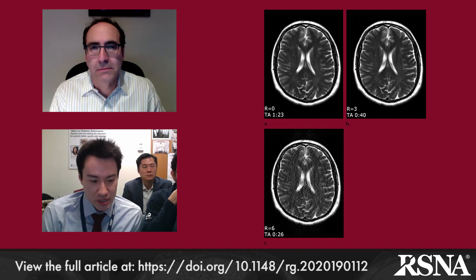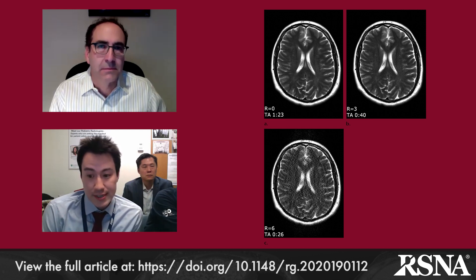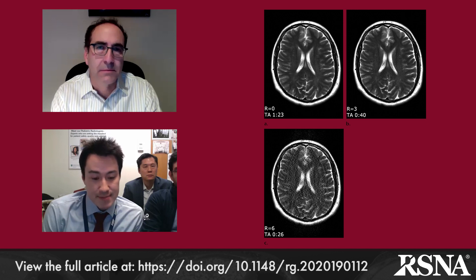There are a number of different strategies to accomplish parallel imaging, some based on eliminating aliasing in the imaging domain, some in the K-space-based domain. All of them are essentially equivalent in terms of imaging reduction time and image quality. The average acceleration you can get is on the order of 1.5 to 4 in current clinical practice, and you can combine parallel imaging with other techniques to achieve even faster imaging times. Parallel imaging can be applied to really any pulse sequence, with the major disadvantage being a reduction in signal-to-noise ratio because you're acquiring less signal. Figure 2 illustrates that point.